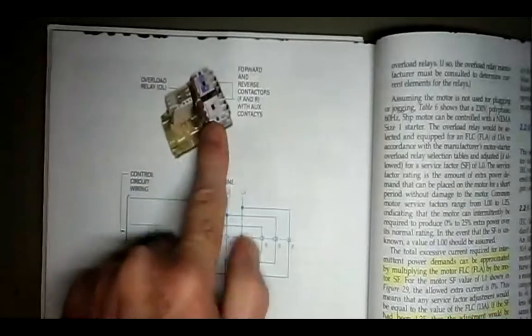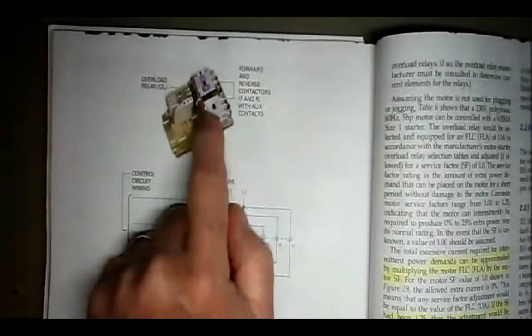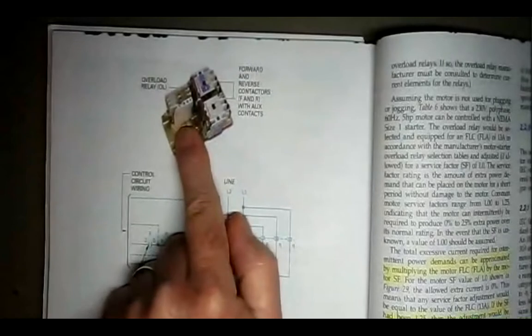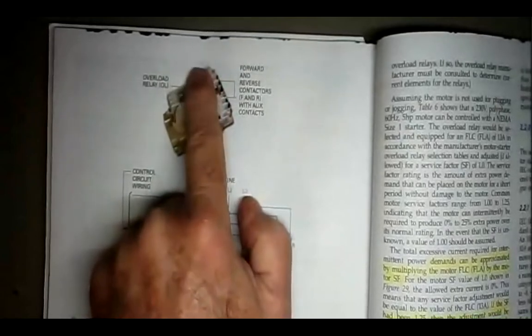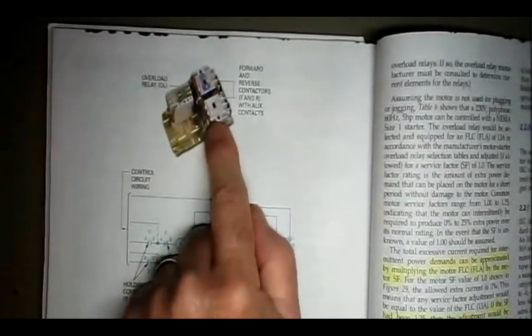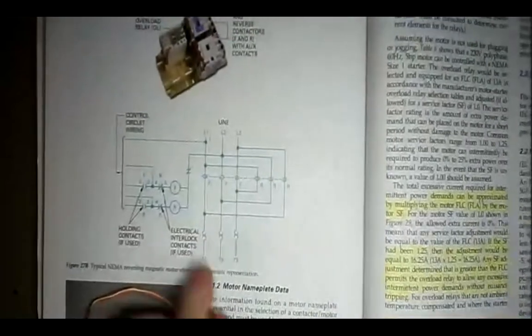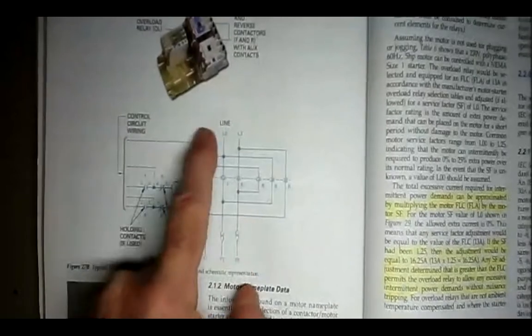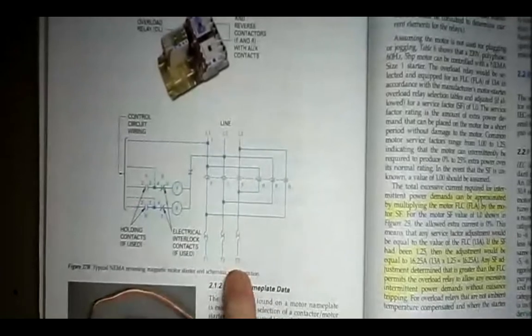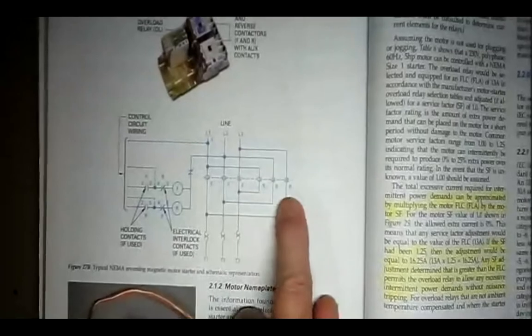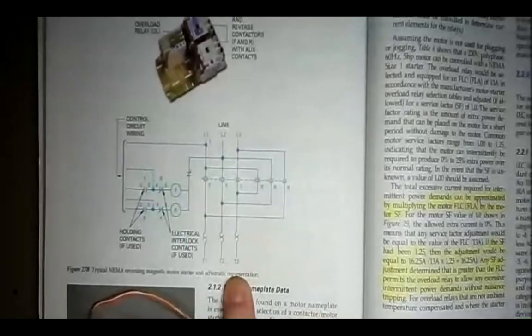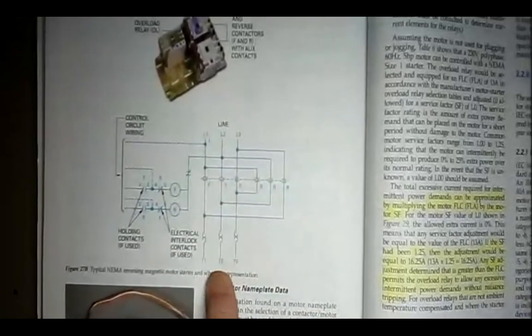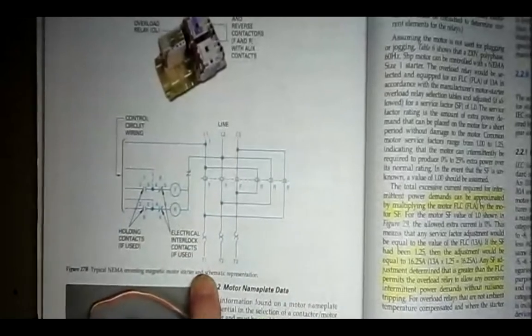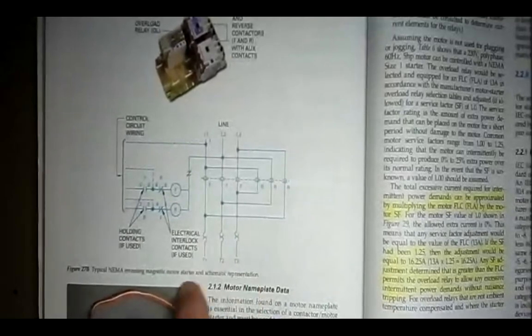Over here on page 24, I don't have a highlight, but this is a good example of a forward reversing starter. They've got two motor starters or two contactors controlling the same motor with one set of overloads. When one of these contactors is closed, the motor will turn clockwise, and they usually call that forward. With the other, the motor will turn counterclockwise, and they usually call that reverse. On the drawing, you can see that when the forward contacts are closed, line 1 goes to T1, line 2 goes to T2, and line 3 goes to T3. When the reverse contactor is closed, line 1 is actually going to T3, line 2 is going to T2, and line 3 is going to T1. So they've changed it from 1, 2, 3 to 3, 2, 1.